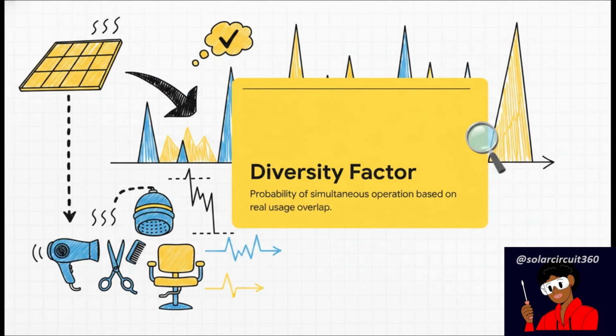And that brings us to a crucial, absolute game changer of a concept, the diversity factor. Simply put, this is the probability of simultaneous operation. When you're trying to model a salon's power behavior, you've got to calculate the real usage overlap, rather than just naively assuming every single device in the building is turned on to the max at the exact same second. In reality, not every hairdryer is running continuously. Not every single station is blasting at maximum load simultaneously.